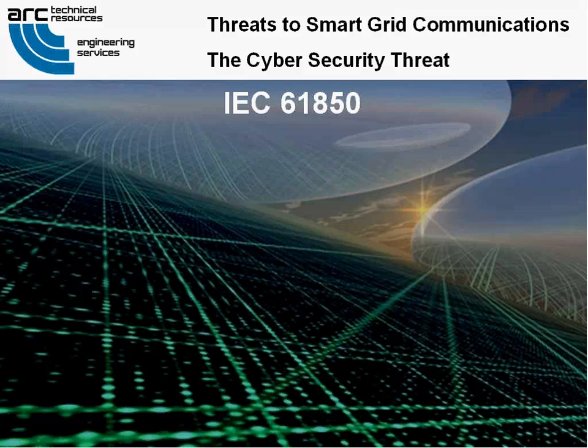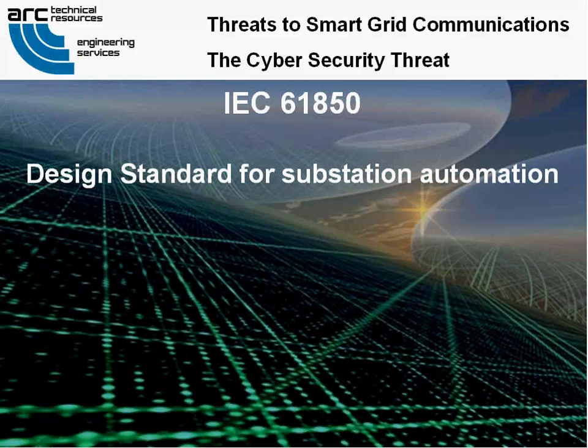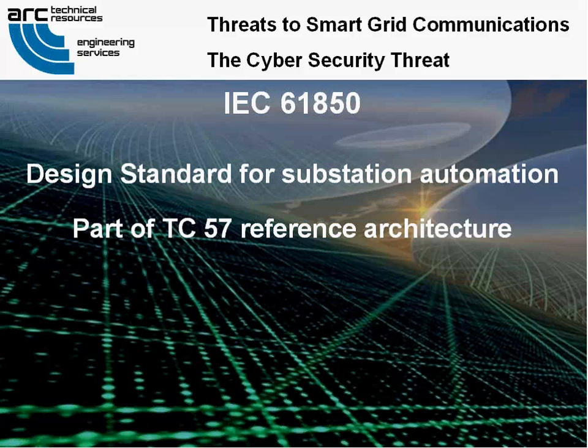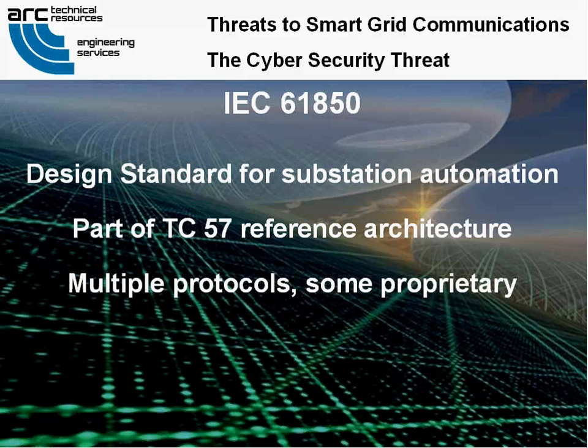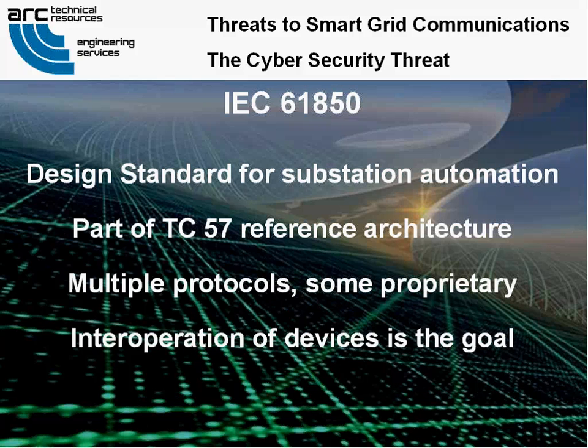IEC 61850 is a standard for the design of electrical substation automation. It resulted from the work of about 60 members from different countries in three working groups starting back in 1995. It is part of the IEC TC57 reference architecture for electric power systems. Multiple protocols exist for substation automation, which include many proprietary protocols with custom communication links. Interoperation of devices from different vendors is important to users of substation automation devices, so the abstract data models defined in 61850 can be mapped to a number of protocols.